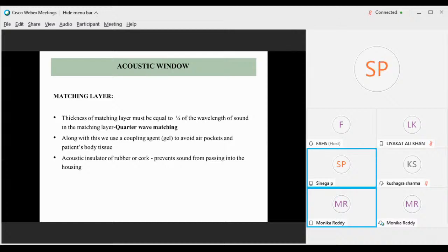So the thickness of the matching layer must be equal to 1/4 of the wavelength of the sound in the matching layer, which is known as quarter wave matching. This matching layer is placed at the front face of the transducer, and it should be equal to 1/4 of the wavelength produced by the transducer. Along with this, we should use a coupling agent or gel to avoid air pockets between the transducer and the patient's body, in order to reduce scattering at the skin surface. An acoustic insulator of rubber or cork prevents sound from passing into the housing.